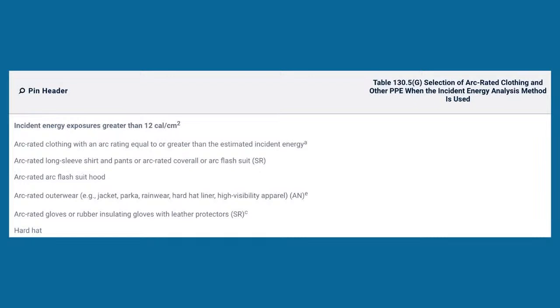So what was that one? Didn't we find one where there was a certain cal rating that you had to wear a face shield? Like, wasn't it 4 cal? Well, you're always going to put the face shield on. The one thing they had to come in and correct was putting on the sock hood, the balaclava, because you had to protect the ears and the back of your neck. Gotcha. But the face shield was always there. Okay? Was that at 4 cal? Yeah. What was that threshold?